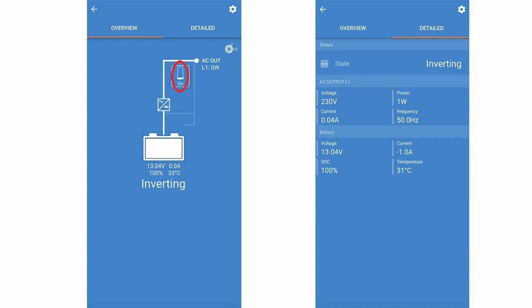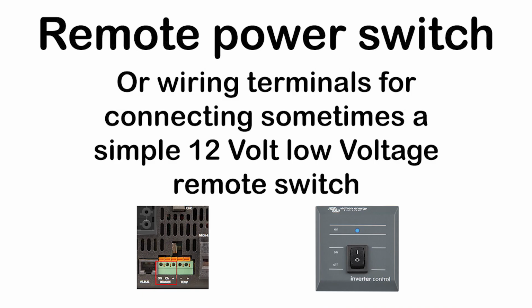If you're, say, running an AC refrigerator and have to keep the inverter turned on, then the power saving mode might help save some power between refrigerator compressor cycles, but that's about it. Or the inverter might facilitate the wiring up of a remote switch. If the physical inverter has been placed in a difficult to access location and the power switch on its casing cannot be accessed, a remote on-off switch may be located somewhere a little more convenient and can be used to switch the inverter on and off manually as and when needed.